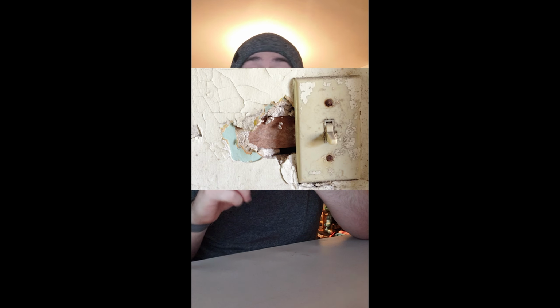Today, I was recently called out because there was an inspection that did not pass for an apartment, and the reason was a broken piece of wall. I'm gonna put something on the screen so you know roughly what it looks like. I wasn't able to get a shot of it, but essentially a little bit of drywall was broken away around the switch, and that's dangerous because with an inch and a half or two, if there's bad grounding or a grounding fault, a kid could potentially reach something metal in there, or somebody who is blind would be reaching for a light switch or feeling along the wall and they could get electrocuted as well. That's a big no no. And so I had to get rid of that.